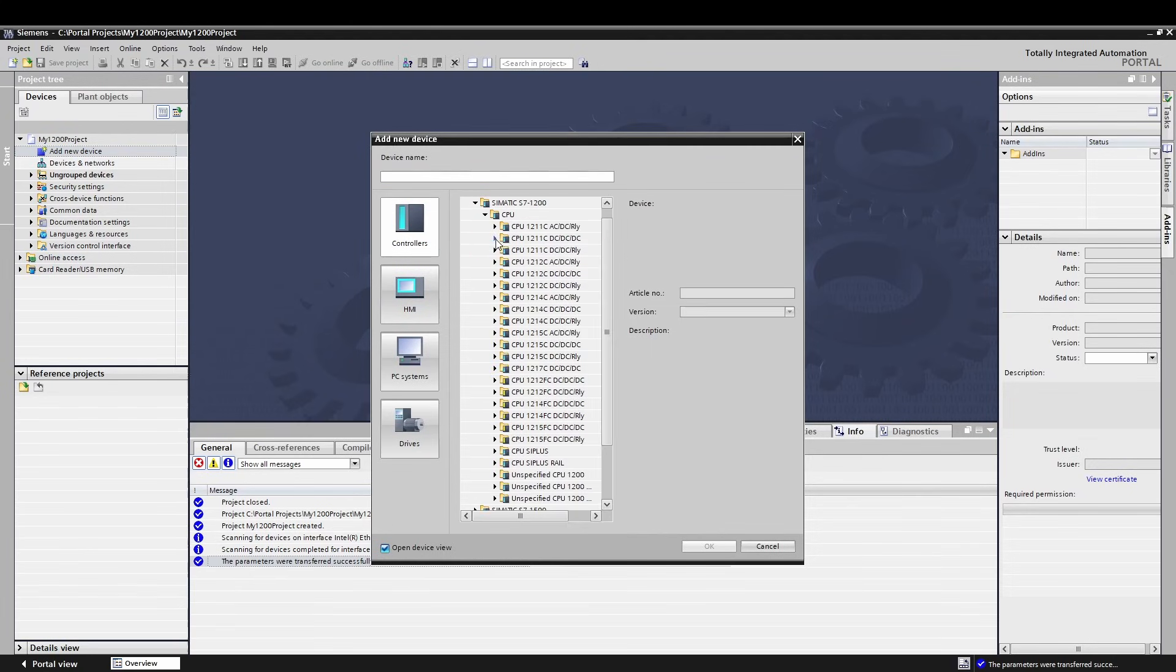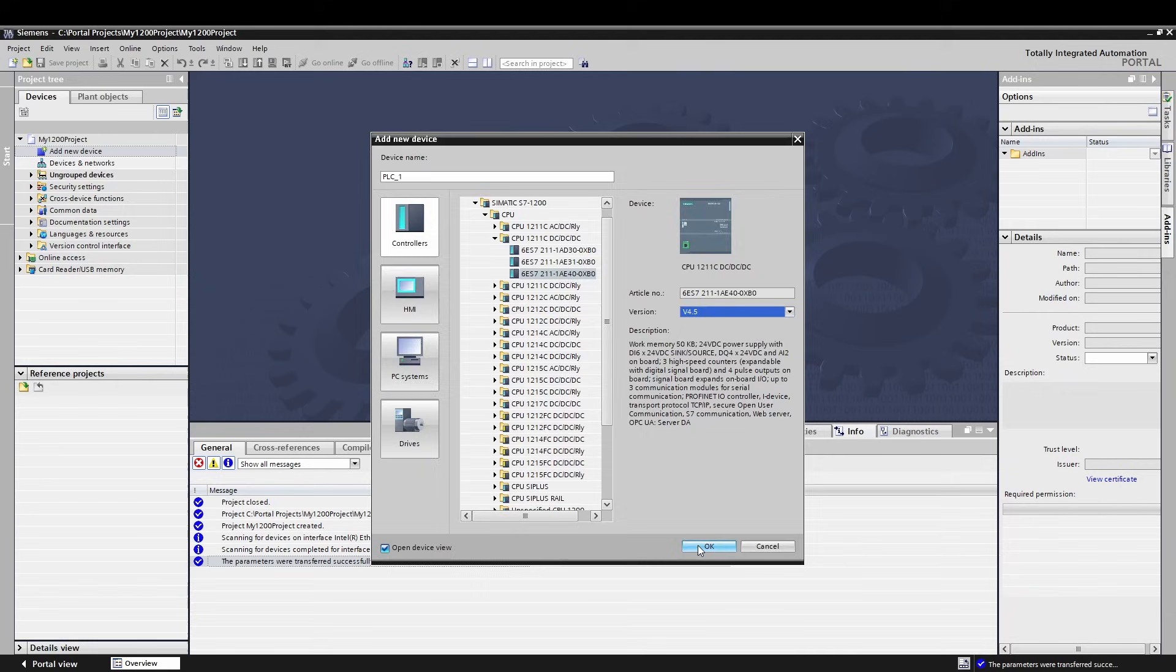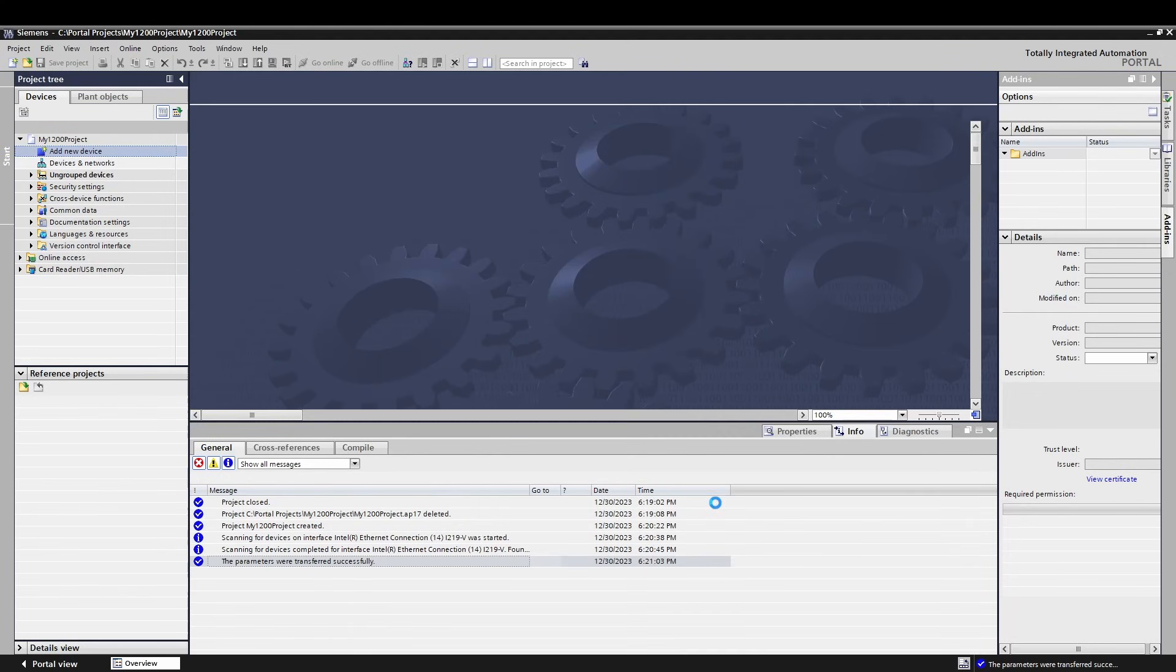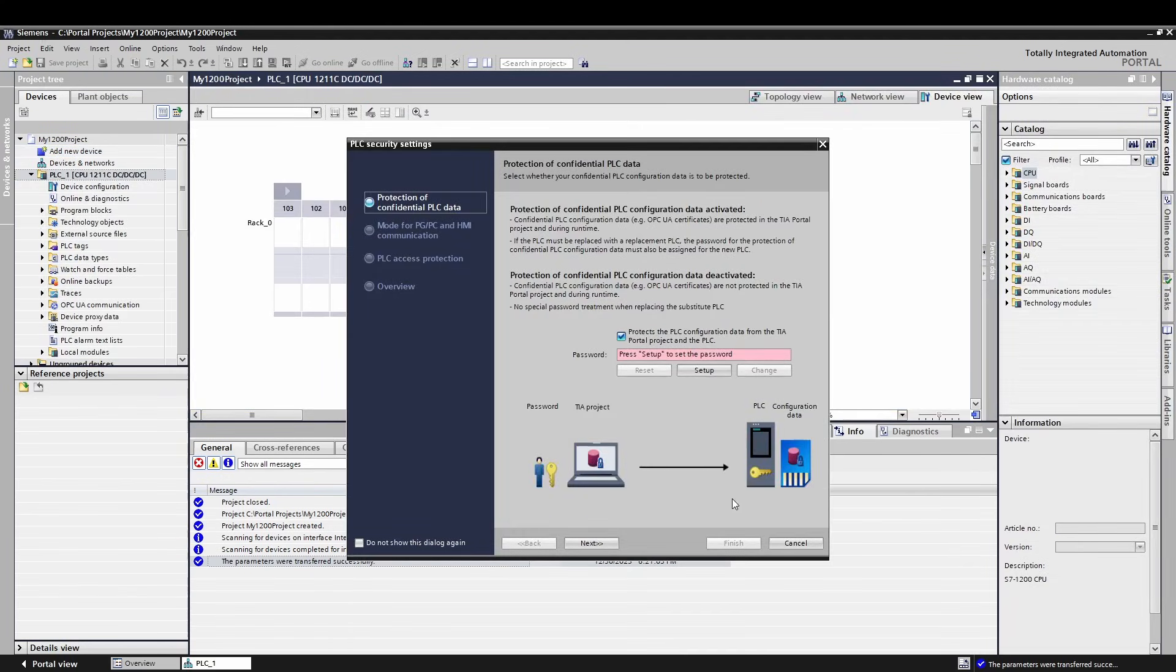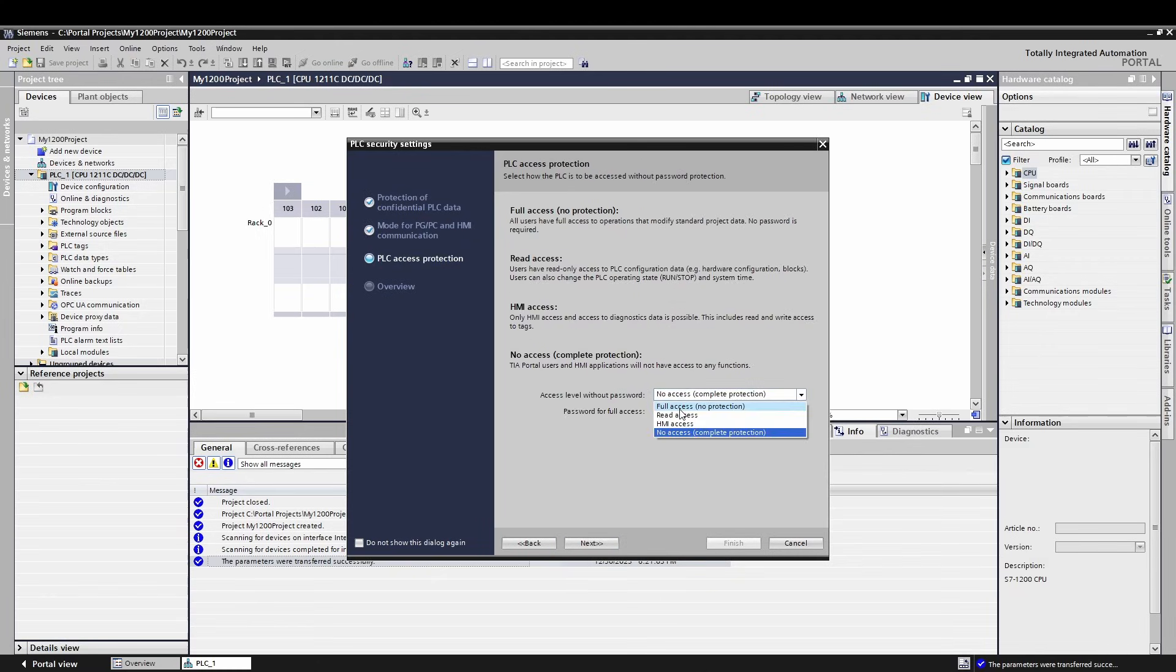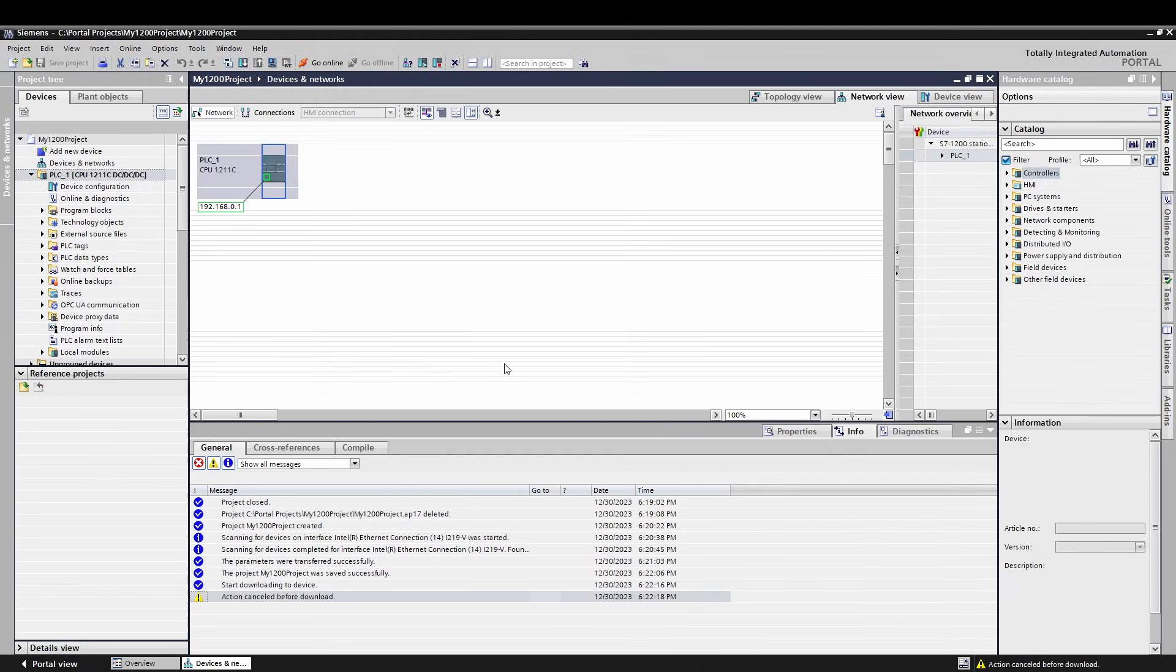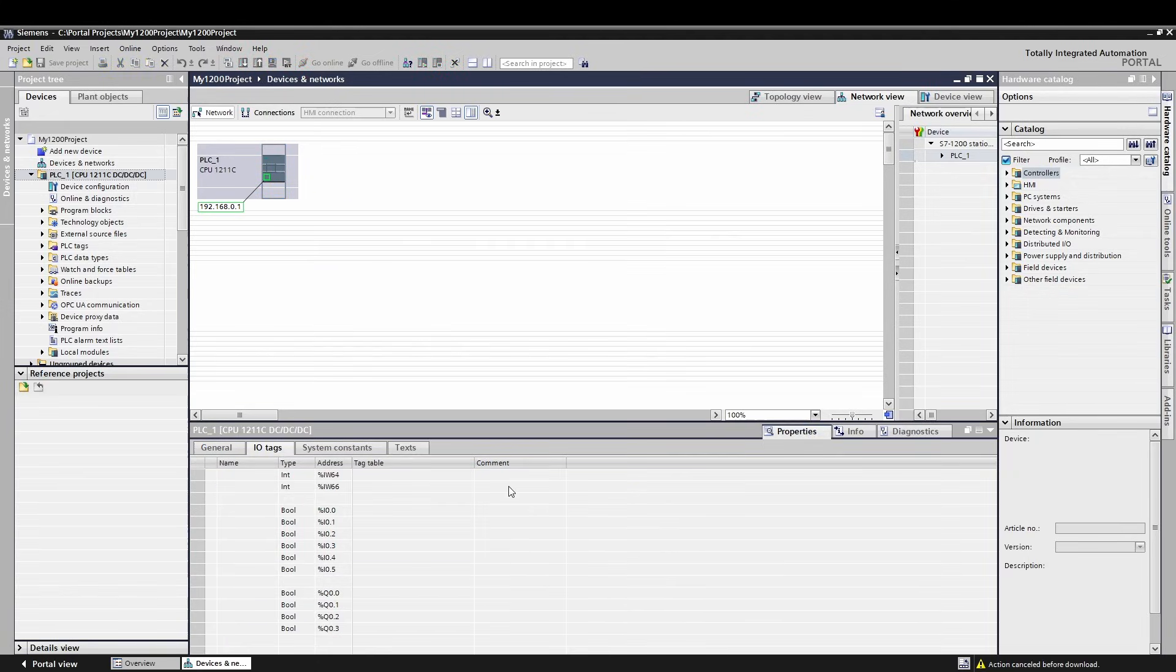If you are connecting to a PLC that's already set up, you may just want to skip this step and write this IP address down for later. Once you have determined the version and firmware of your PLC and you have set the IP address, let's add this to our system by selecting Add New Device and selecting PLCs, S7-1200, 1211 DC/DC relay, and making sure we select the correct firmware that is sometimes hidden down in the bottom right corner.